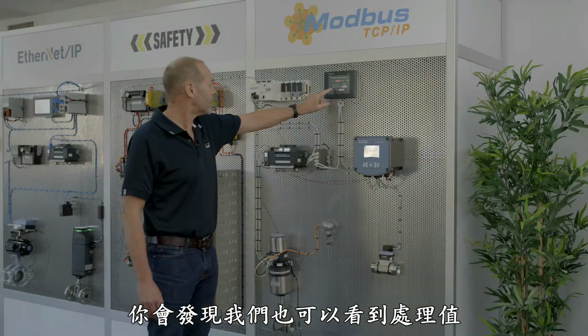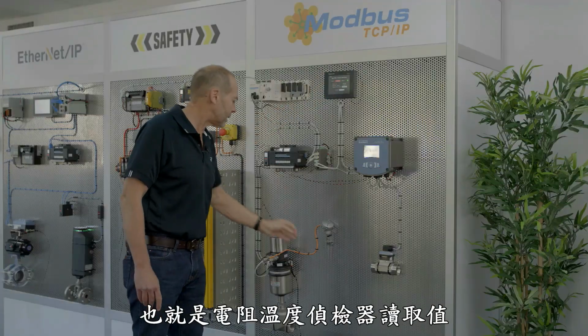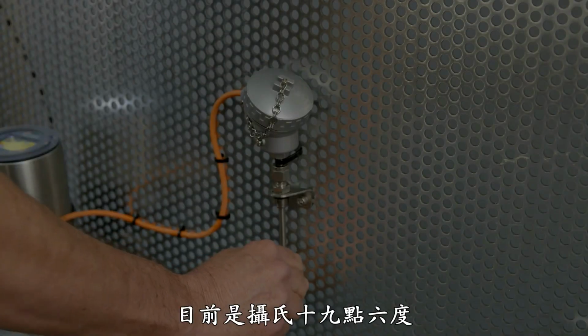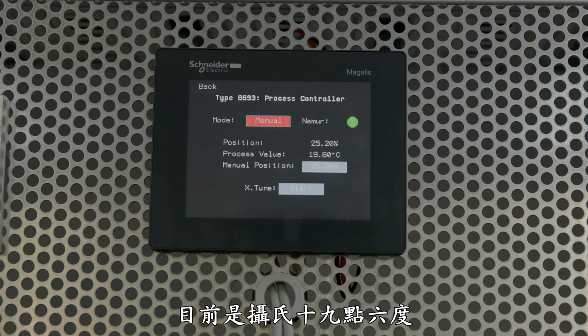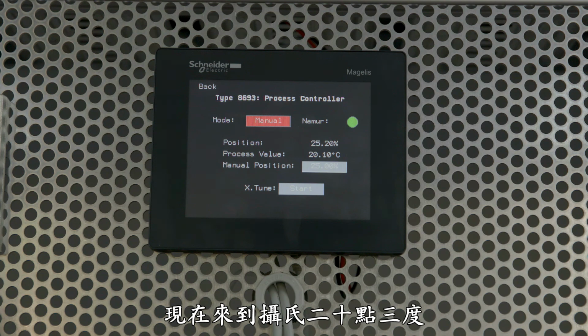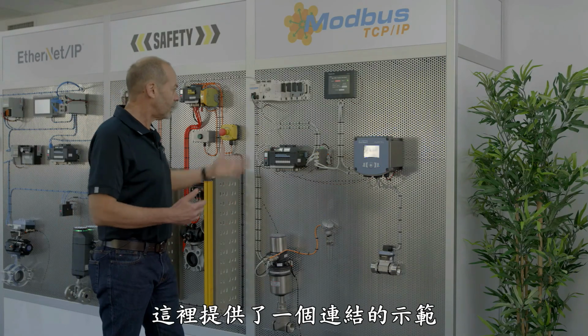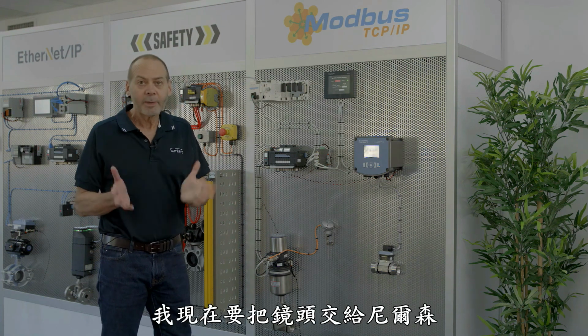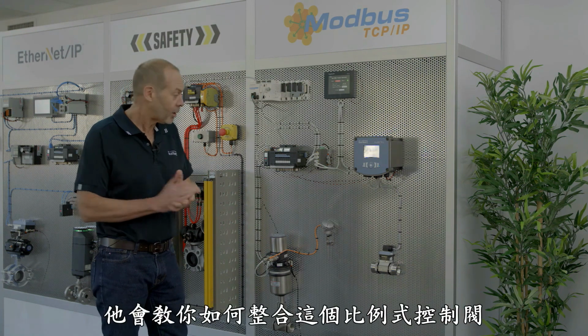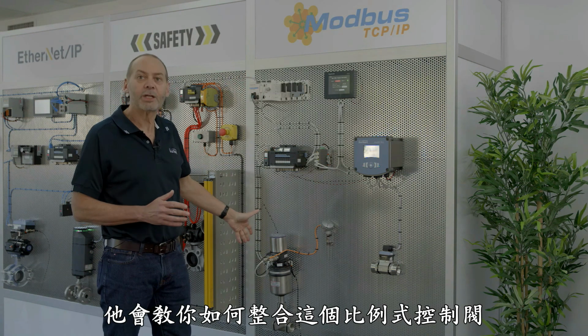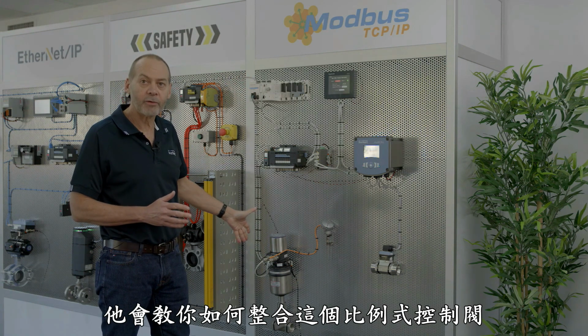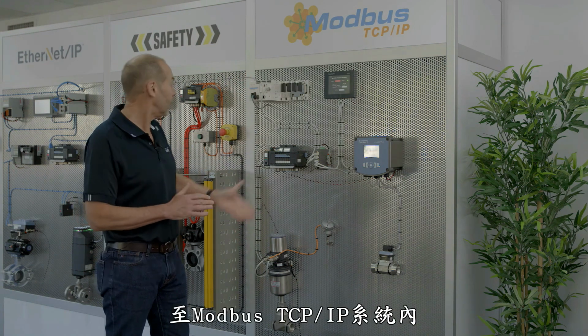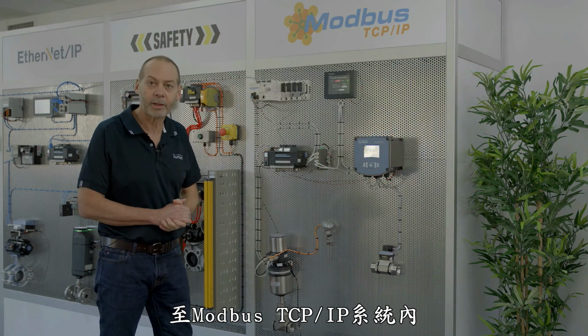And of course you'll notice that we can also read the process value, which is the RTD. If I put my fingers on that, you'll see it's at 19.6 degrees. It's a little cool in this room. And now it's up to 20.3. So this gives you an idea of the connectivity. I'm going to hand you over now to Nelson Chimiak, who's going to take you through the integration of this modulating control valve into the Modbus TCP/IP network.